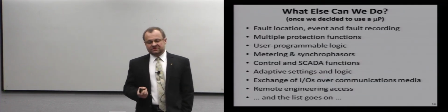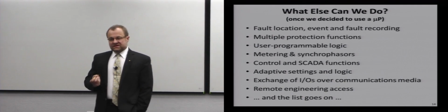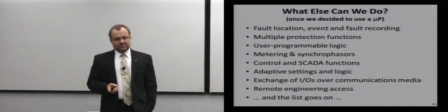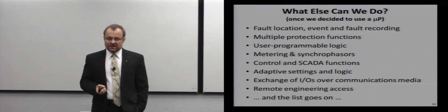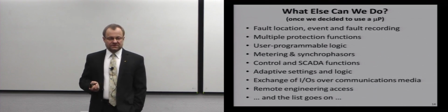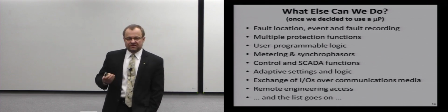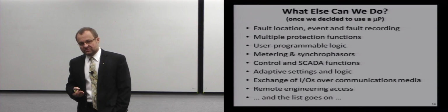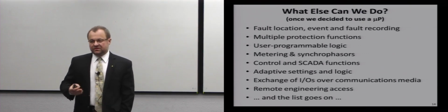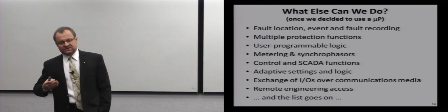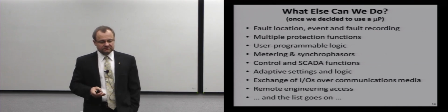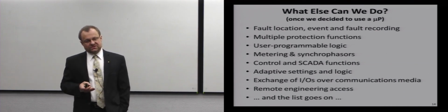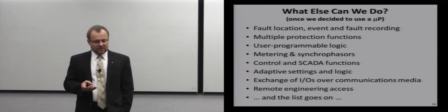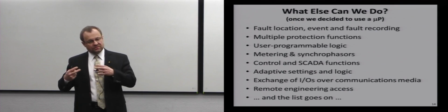Now, the beauty of this is this. Once we use the microprocessor to do protection, what else can we do? Well, we could locate the fault. We could process that current and voltage and give a very accurate estimate, to within a couple of percent, of where the fault is, so we could dispatch the crew and start fixing the line. We could put multiple protection functions in the same relay. We could do the wiring between the protection functions.